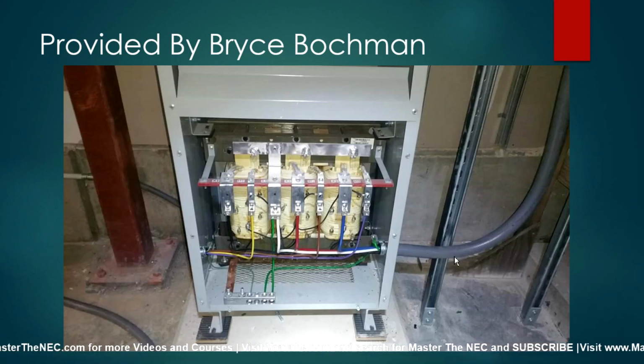So again, you're not using this as the supply side bonding jumper. So it connects to a punched hole. So I don't see the need for you to do anything. A regular lock nut would work fine because again, all you're doing is bonding it. Okay. And you could come in and you make your connections here. Another thing to notice that 450.10 won't allow you to make any type of connections over top of the vent holes. So any of these terminations right here can't be through the vent holes. I've seen people actually do it because they can stick a bolt through it and make the connection in here.